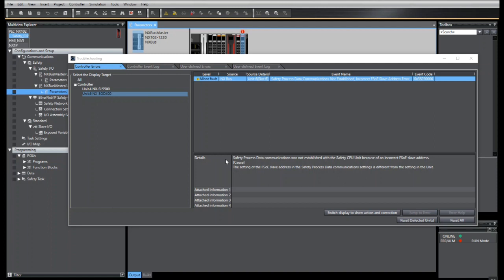Today, I will demonstrate how to correct the FSOE slave address error on an NX safety slice. This may occur if the card has been pre-commissioned and been given a slave address error and has been reintroduced into an existing system.